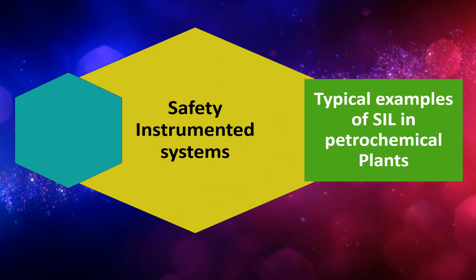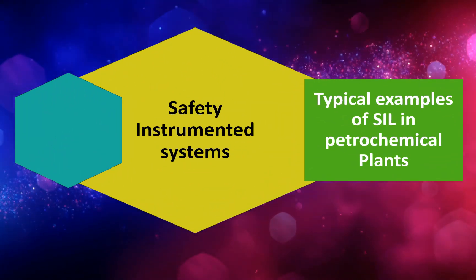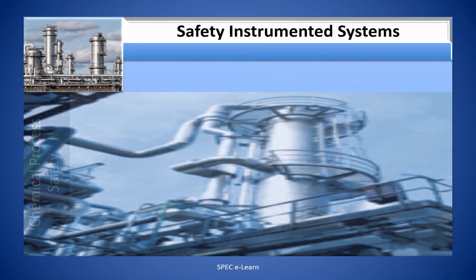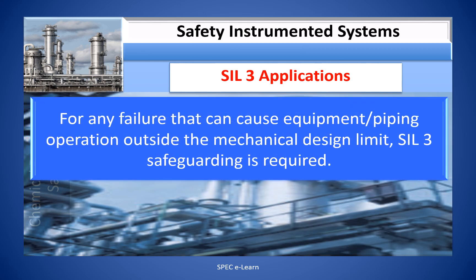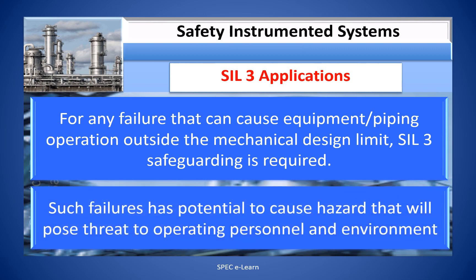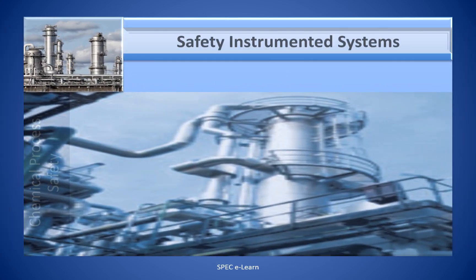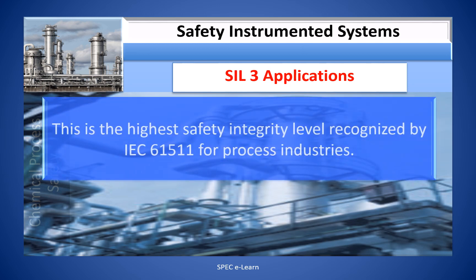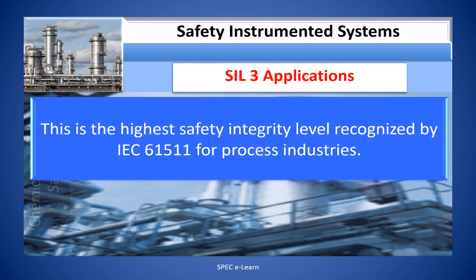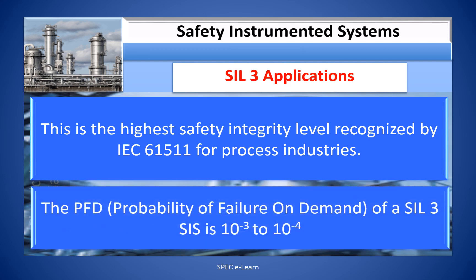Typical examples of Safety Integrity Levels in petrochemical plants. SIL 3 example: for any failure that can cause equipment and piping to operate outside the mechanical design limit, SIL 3 safeguarding is required. Such failures have the potential to cause hazards that will pose a threat to operating personnel and the environment. This is the highest safety integrity level recognized by standard IEC 61511 for process industries. The PFD of a SIL 3 SIS is 10 to the power of minus 3 to 10 to the power of minus 4.